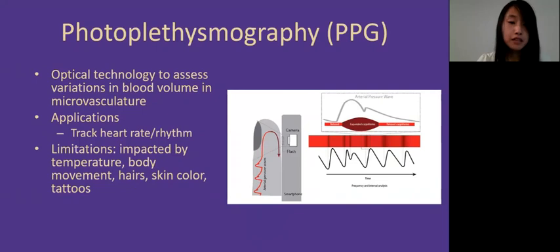Another piece of familiar technology is photoplethysmography, or PPG. It's the same technology used in pulse oximeters, which is optical technology that detects variations in blood volume within the microvasculature. It can work with existing cameras within smartphones or be an accessory device as a separate sensor. By measuring the pulsatile activity of the microvasculature, it's able to detect the heart rate and heart rhythm. Since a lot of this technology is dependent on light penetration, the measurements can be impacted by body movement, body temperature, body hair, skin color, and even tattoos.